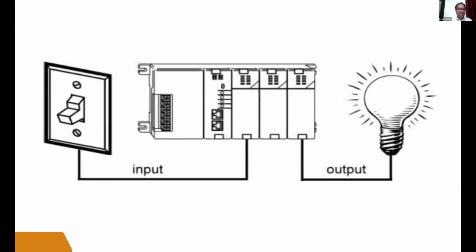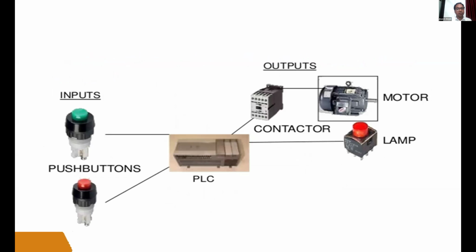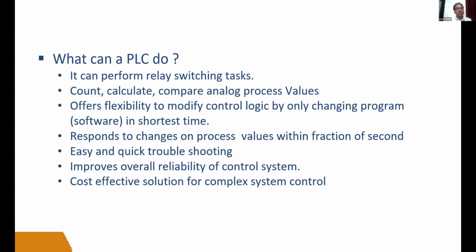But if you are using the PLC, at that time, there is no need to make the change in your connection. You will make the change in your program only. That's why PLC is called the software system. Now see here how exactly PLC works. This is the input side, main PLC, and that one is the output side. It performs the relay switching task, counts, calculation, comparison, analog process value. Analog means temperature, pressure, humidity, etc. It offers flexibility to modify the control logic by only changing the program. It responds to change in a process value within a fraction of a second. Easy and quick troubleshooting. Improves the overall reliability of the control system. Cost-effective solution for complex problems.